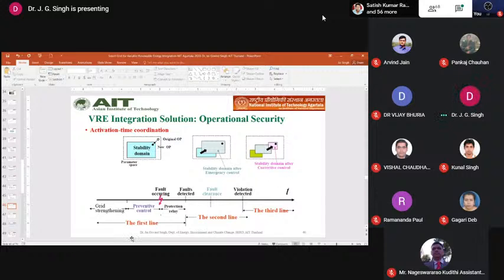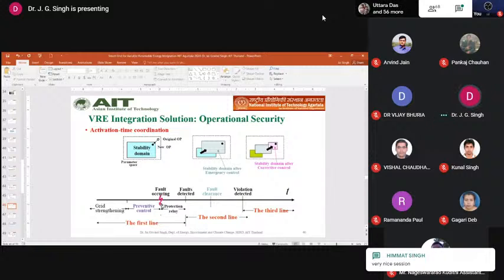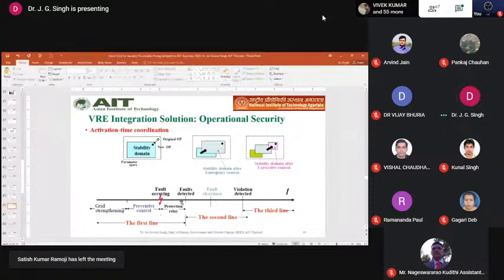In case of the first line defense, the long term involves grid strengthening options or solutions. Then there's preventive control where always possible. Suppose at this instant a fault occurs; using traditional relays and circuit breakers, it takes about 1 to 2 cycles in the relay, 1 to 2 cycles to open the contact, and 1 to 2 cycles for the arc extinction process, so altogether about 5 cycles.